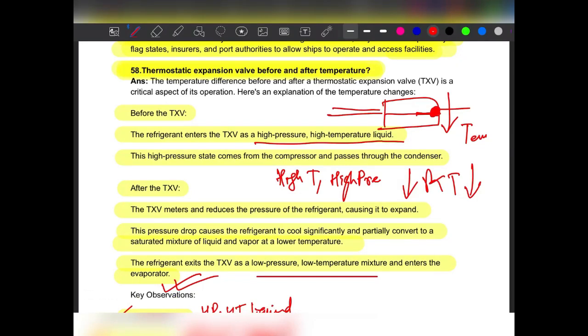It basically senses the temperature. If the temperature is not according to the set point, it will open the valve. Suppose your set temperature is 5 degrees Celsius, and now the temperature inside your chamber is 8 degrees Celsius, then there is a 3 degrees Celsius difference. So what will happen?